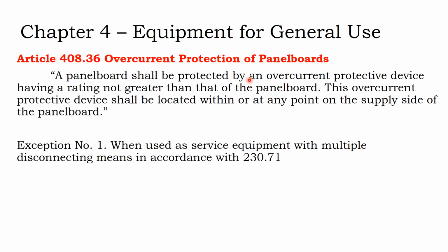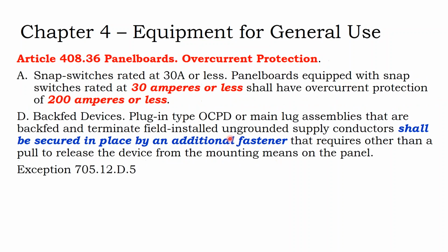And then when we get into larger panel boards, we say a panel board shall be protected by an overcurrent protective device that has a rating not greater than that of the panel board. This overcurrent protection device should be located at any point on the supply side of the panel board. So if you have a 200 amp rated service panel, you put a 200 amp main breaker on it, you're no longer getting into that upsizing to the next nearest breaker. Your main overcurrent protection device should protect you from drawing in too much current and not create a safety hazard by allowing you to draw in 250 amps when it's only rated for 200.